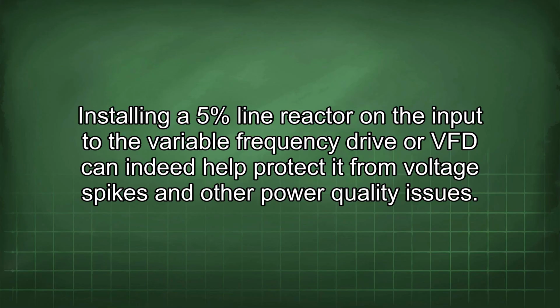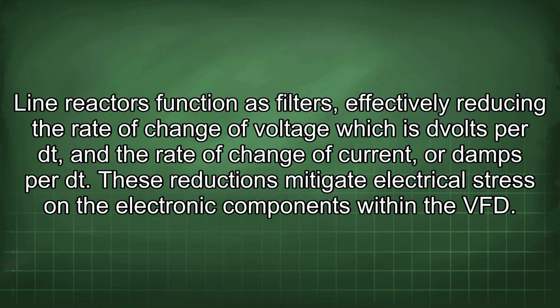Installing a 5% line reactor on the input to the variable frequency drive, or VFD, can indeed help protect it from voltage spikes and other power quality issues. Line reactors function as filters, effectively reducing the rate of change of voltage, which is dV per dt, and the rate of change of current, or dI per dt. These reductions mitigate electrical stress on the electronic components within the VFD.